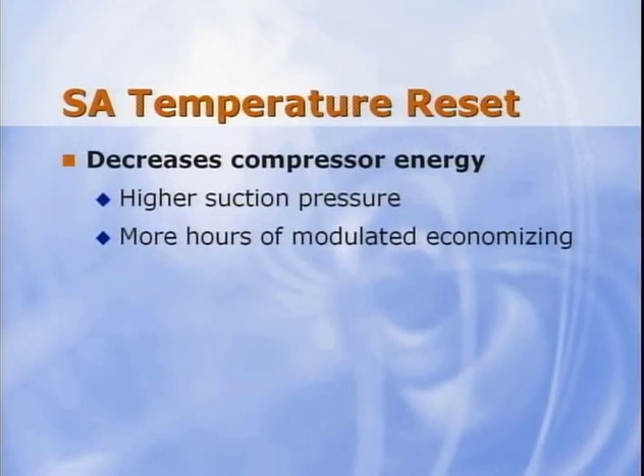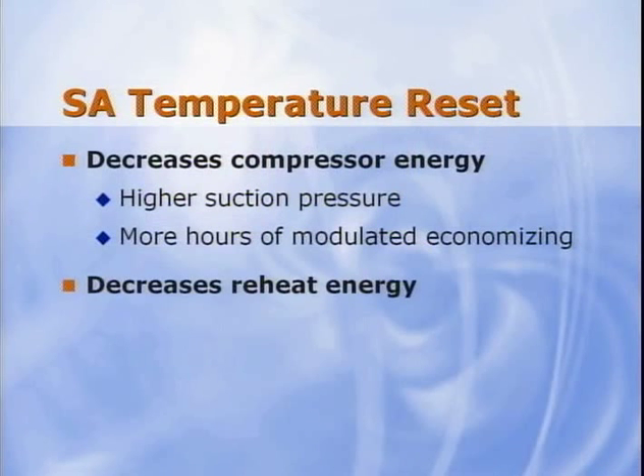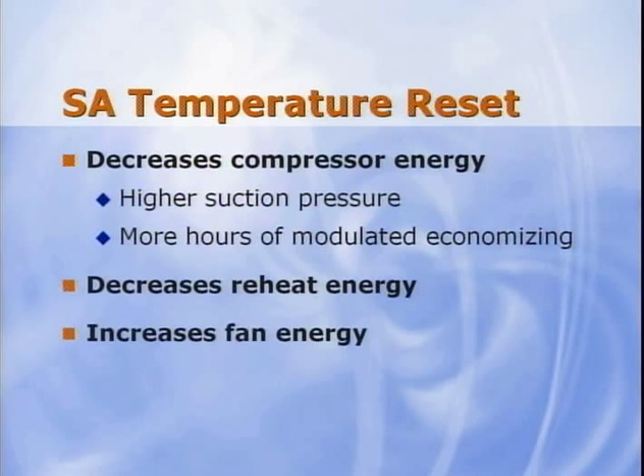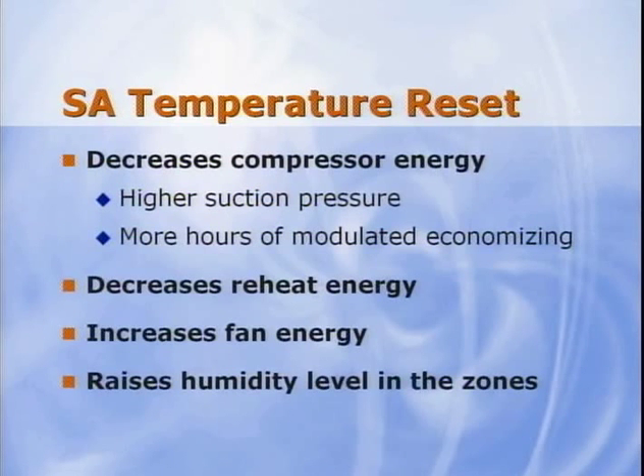For those zones with very low cooling loads, where the supply airflow has been reduced to the minimum setting of the VAV box, raising the supply air temperature also decreases the use of reheat energy. However, because the supply air is warmer, those zones that require cooling will need more air to offset the cooling load. This increases supply fan energy. Finally, in non-arid climates, warmer supply air means less dehumidification at the coil and higher humidity levels in the zones. So, if dehumidification is a concern, use this strategy with caution.